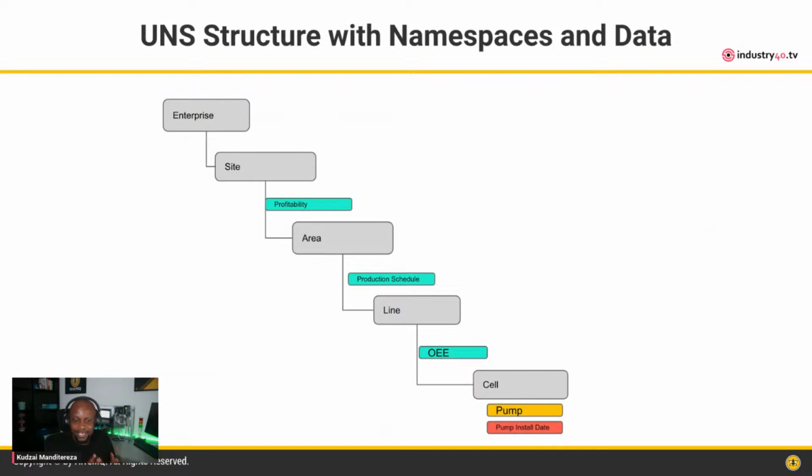So you have that pump announce itself when it joins the network by publishing a birth message. If it's Sparkplug, that birth message will indicate all the metrics that the pump is going to be publishing. So it is crucial for that pump to publish a birth message that notifies all the other participants, or importantly, the SCADA system, that it has joined the network.